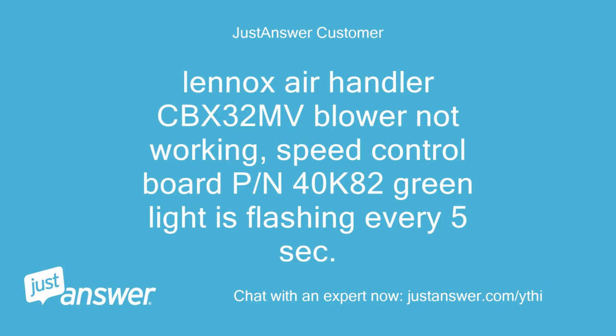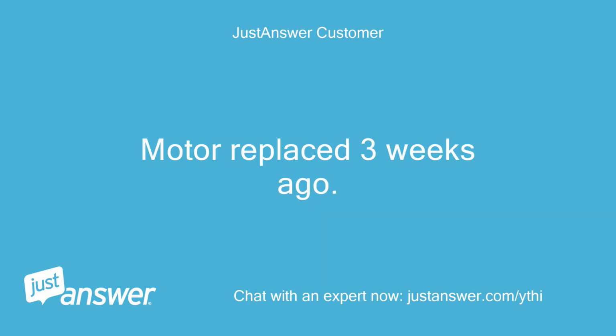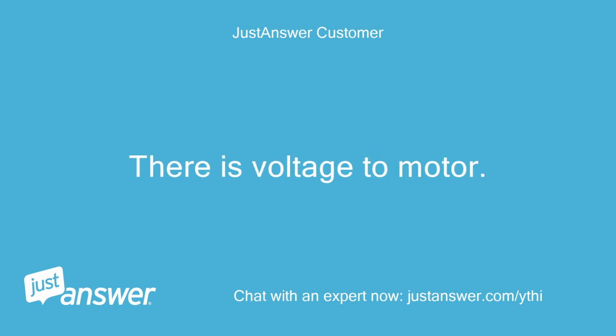Lennox air handler CBX32MV blower is not working. The speed control board PN 40K82 has a green light flashing every 5 seconds. The motor was replaced 3 weeks ago, and there is voltage to the motor.